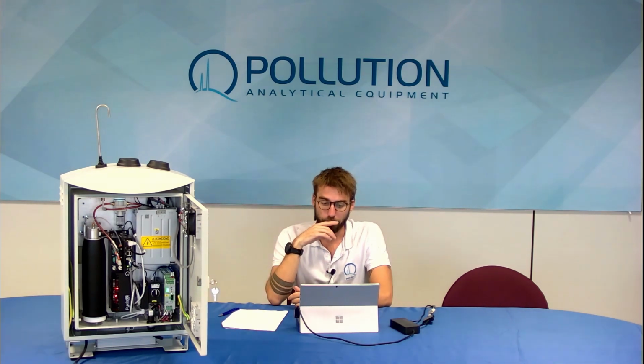Today I'll talk about the manual calibration and how to calibrate the PyxisGC with external gas cylinders. In order to manually calibrate, you need to buy a certified gas cylinder with BTEX compounds in it. Then, by using a dilution system, you need to dilute this gas tank to your desired concentration for the calibration. Usually, the calibration could be around 30 ppb of benzene, or maybe above 100 ppb if you want to get a calibration of a higher concentration analytical methods.